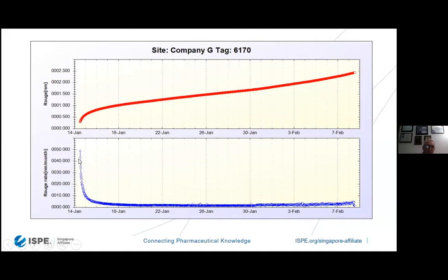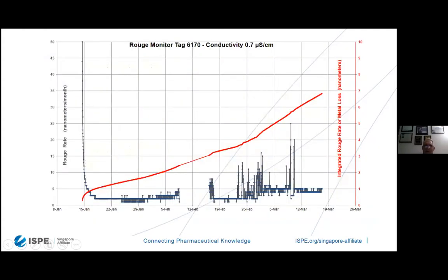Also showing on January the 14th installation, it takes about 24 hours for the probe to acclimate itself inside the water system. And then you can see the accumulation starts from there, very, very small, showing indications around 1 or 2 nanometers. In order to look at this on a longer data period, same installation date. Red line, once again, is accumulation over time.